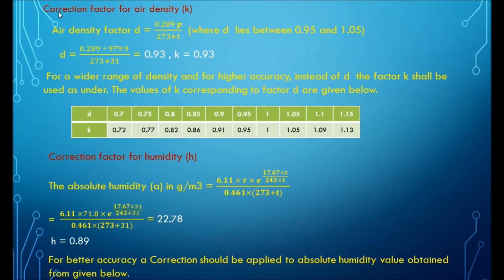Then the calculation for air density. This is the formula. You can calculate the air density, and this is the D value and the corresponding K is here. The D value is 0.93. This is also 0.93, because you can see this is 0.9, 0.91 and 0.95. Then I have taken the reading as 0.93.